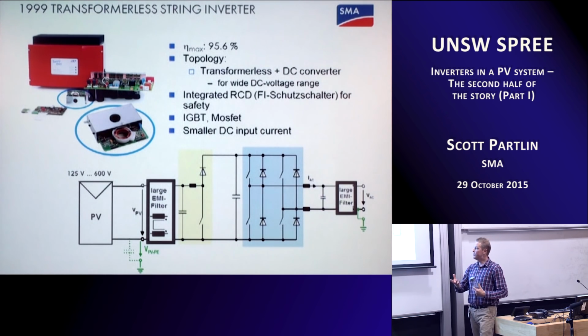The major efficiency gain for inverters came when they moved from being transformer-based to transformerless. Part of the reason for that move is because a transformer is inherently inefficient - there's quite a lot of heat loss and quite a lot of material in there.